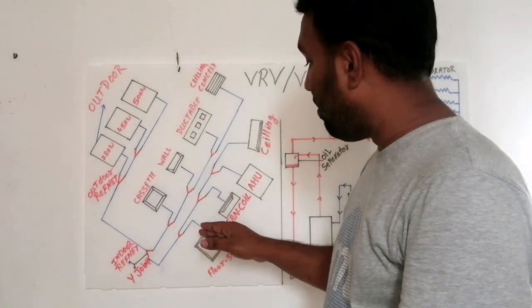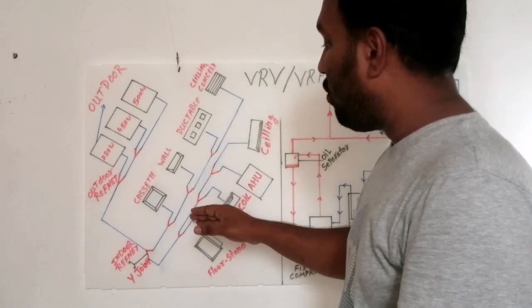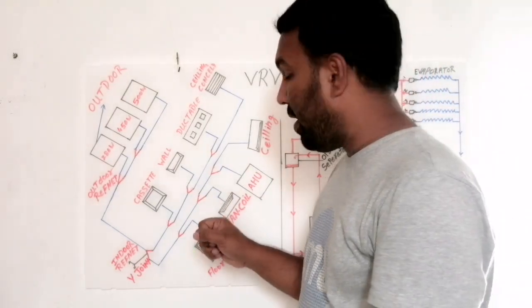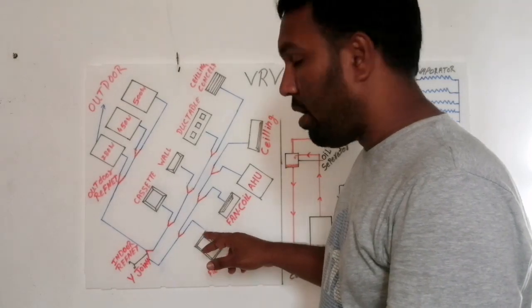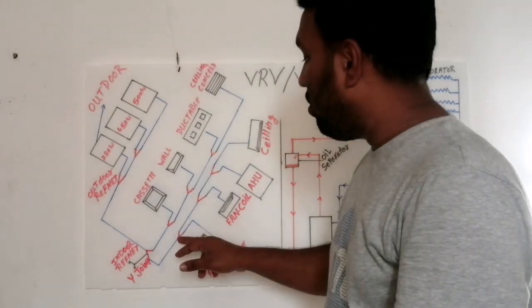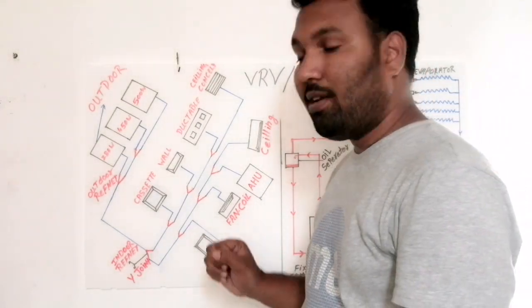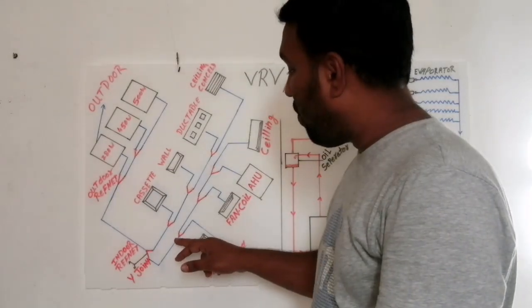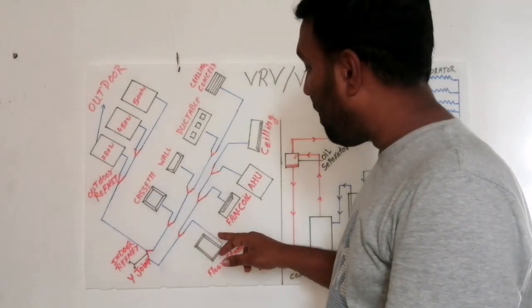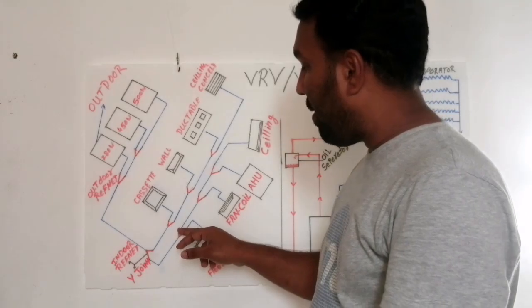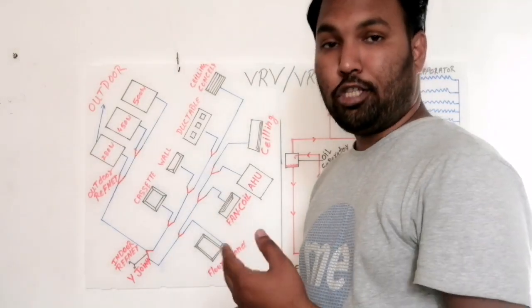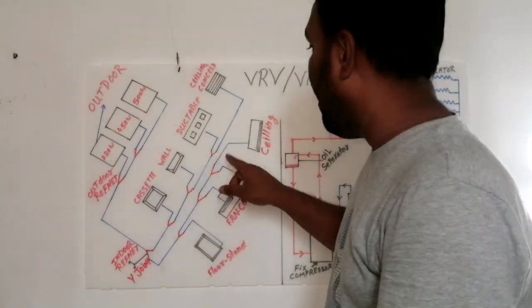Then, according to the indoor units, we have to place our Y joints. Whenever we have to install one indoor unit, before that we have to install one Y joint. When we install one Y joint here, one pipe goes to the indoor unit, and the next pipe continues to the next indoor unit, as you can see here.